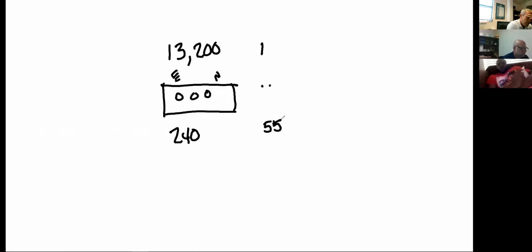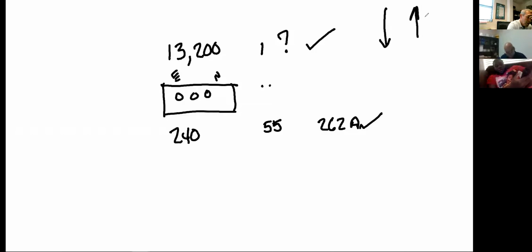155. Now we're going to go the opposite direction in our calculation. I'm down here at the service side, and I measure 262 amps. All right, that's my amp value on the bottom. Now I want an amp value at the top. What's the math involved now? Divide it. Right, if I multiply going down, I divide going up in my calculation. I'm looking for the up number: 262 divided by 55.